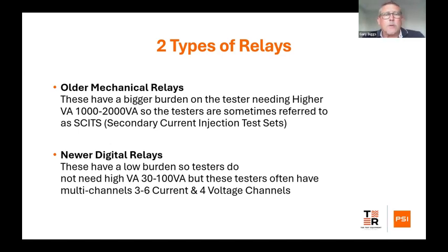In more modern times, we've got newer digital relays, and they're very, very different. The older relays were operated by the system that they were monitoring, so they took their power from the system. So when you needed to test them, you needed quite a powerful test set. Newer digital relays are, as they say, digital, so there's very little burden, and they do not need anywhere near the VA that you would have on an old mechanical type relay tester, and therefore they can be smaller, lighter, more portable, and invariably they'll have 3, 6, maybe 8 channels to them.